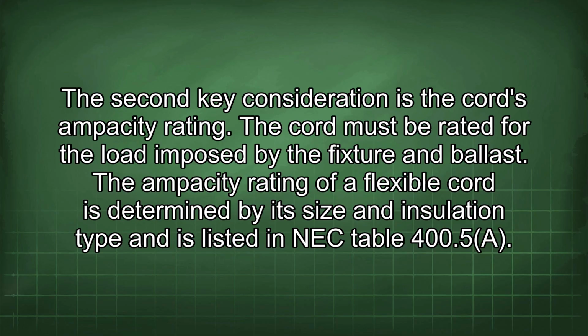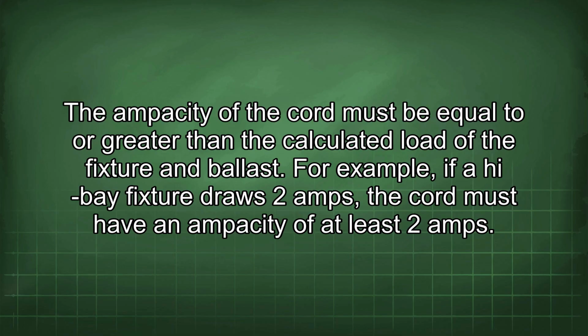The cord must be rated for the load imposed by the fixture and ballast. The ampacity rating of a flexible cord is determined by its size and insulation type and is listed in NEC Table 400.5(A). The ampacity of the cord must be equal to or greater than the calculated load of the fixture and ballast. For example, if a high bay fixture draws 2 amps, the cord must have an ampacity of at least 2 amps.